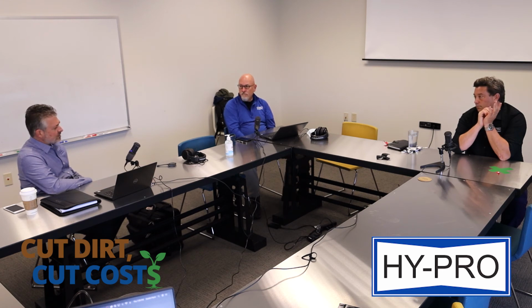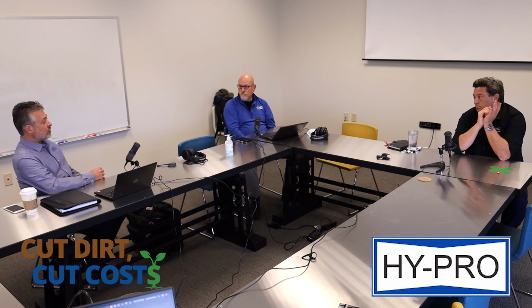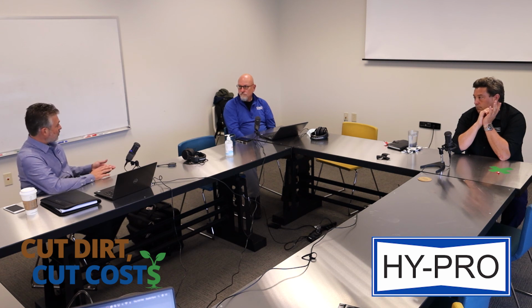So the ICB technology, ion charge bonded technology, it's going to remove the dissolved oxidation byproduct out of the oil. Then we're going to use the oil to help clean the system. Correct. So the oil will then go back out through the system and will start to redissolve this insoluble oxidation byproduct. It's what I would say it's a slow process, but it's a thorough process. It's a complete process. It's not going to be instant, but as soon as the ICB technology is employed, you're stopping the progression, and then we're starting to reverse the effects.